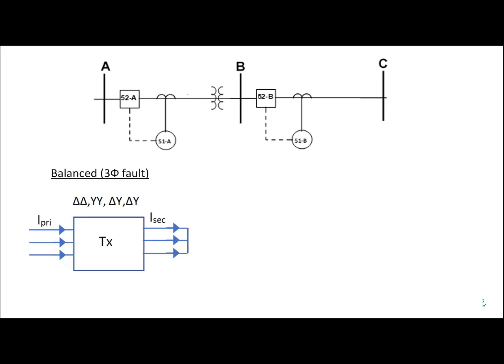Looking at the single line diagram, I'm going to draw and label I_primary and I_secondary. If we have a three-phase bolted fault at bus C, current is going to be flowing from the source to the fault and it's going through the transformer. What we want to do is calculate what the primary current is when the fault is on the secondary side and it's a three-phase bolted fault.